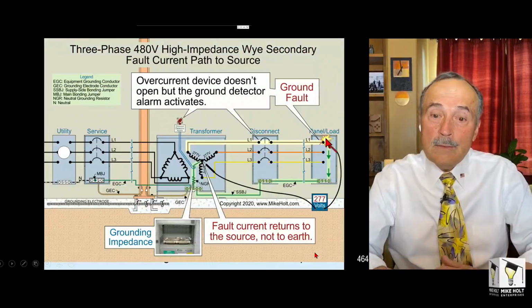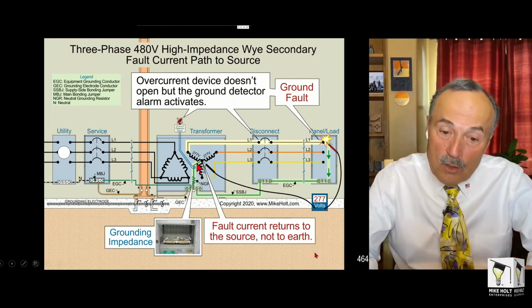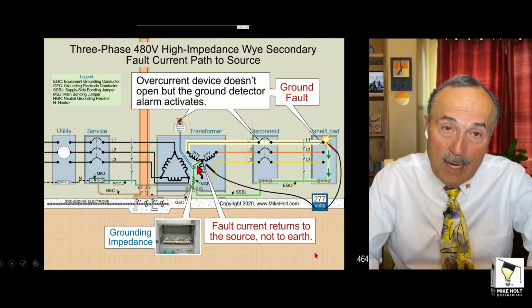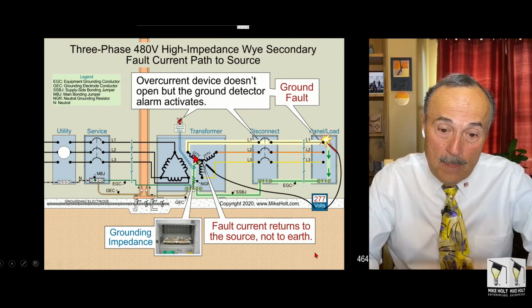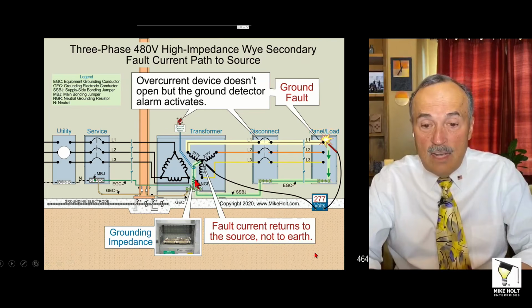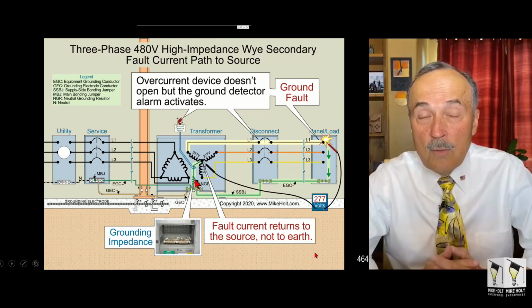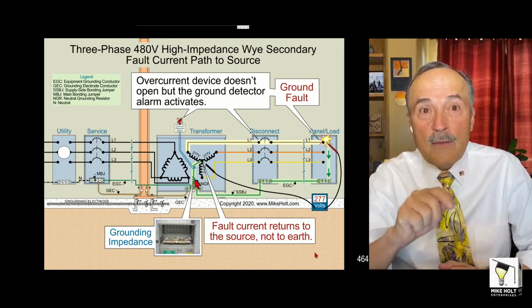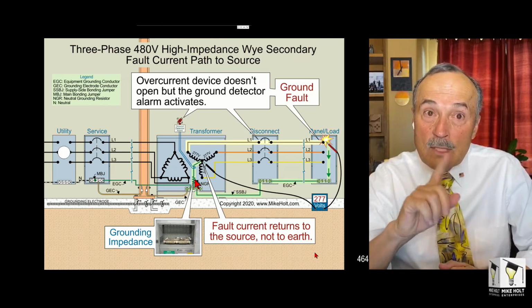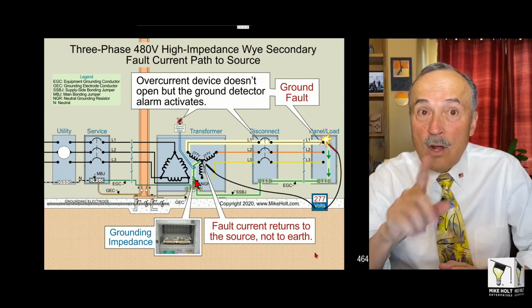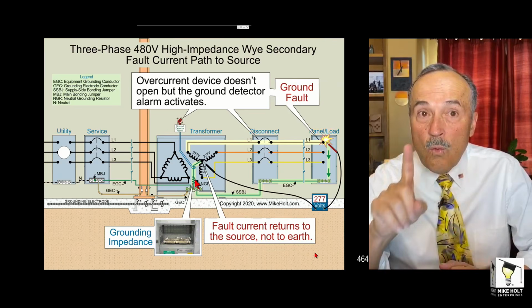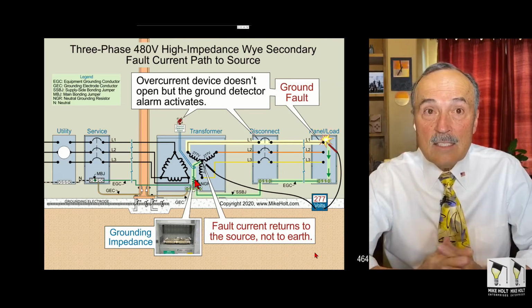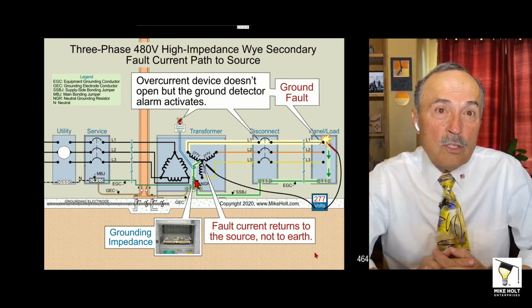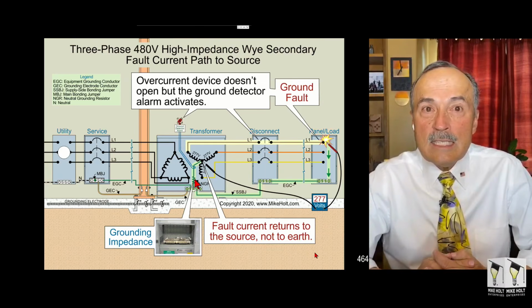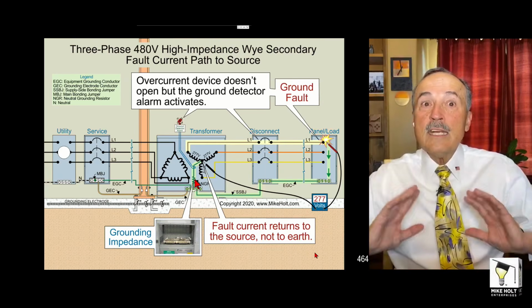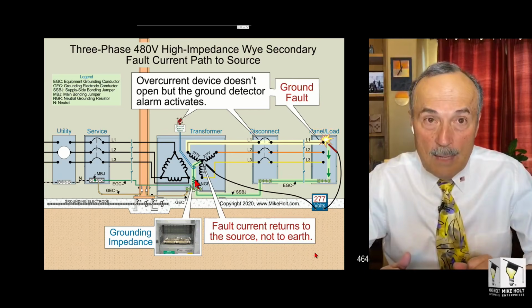How do you clear a fault? Well, anytime there's a ground fault, the key here is what, guys? If you don't have a system bonding jumper, you're not clearing a fault. And if you had a fault at 277, and if this resistor is 277 ohms, then what's the current of that fault? I equals E over R, E is 277, R is 277, 1 amp. Now that is the system you want to install to reduce any kind of arc incident energy, at least when it comes to a single phase ground fault application.